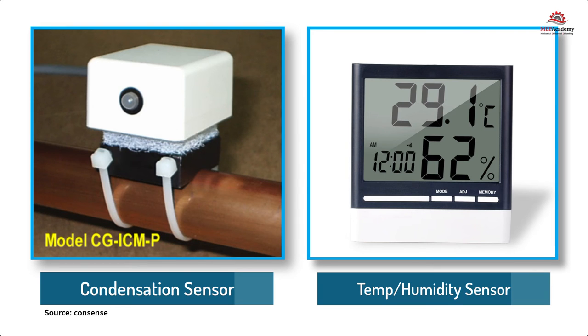Dew point transmitters are used to sense space dew point levels to avoid condensation in rooms where chilled beams are installed. Since chilled beams are designed to avoid condensation and are installed without condensate drain piping, avoiding condensation is critical. Moisture sensors can be strapped to the chilled water piping to indicate the presence of moisture, allowing a signal to be sent to the control valve to stop the flow of chilled water to the chilled beam as a precautionary measure.